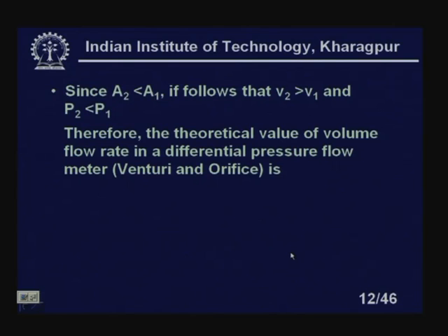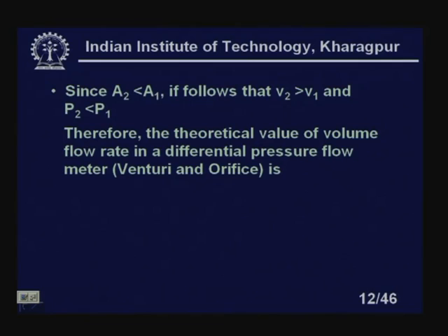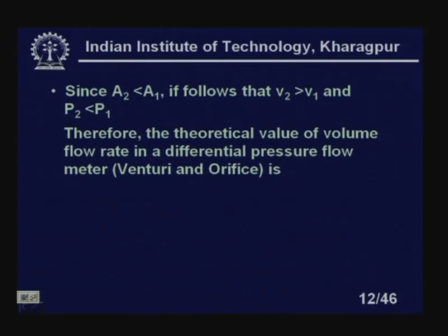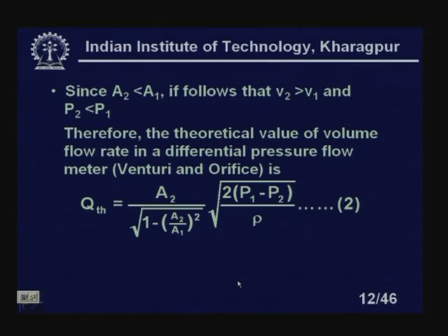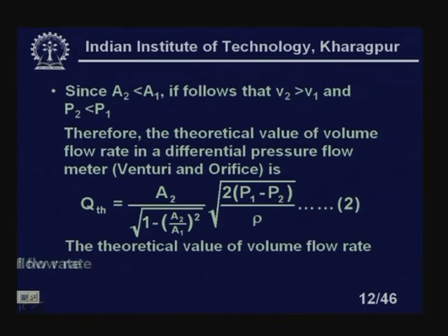Since A2 is less than A1, V2 is greater than V1 — the flow velocity at the restriction is higher than the actual pipe flow velocity. The theoretical value of the volumetric flow rate for both venturi and orifice is: Q_theoretical = A2 / √(1 − (A2/A1)²) × √(2(P1 − P2)/ρ). This is equation number 2.